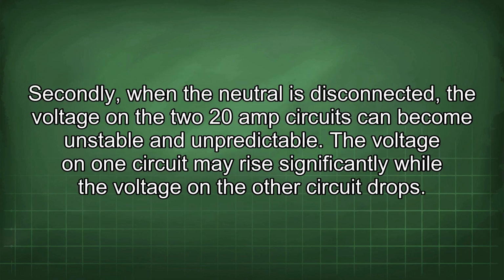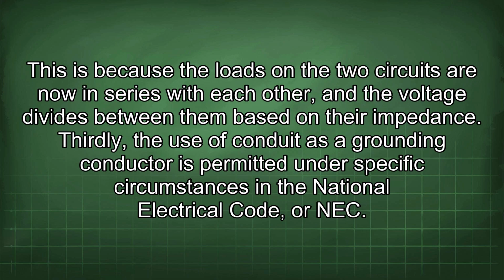Secondly, when the neutral is disconnected, the voltage on the two 20-amp circuits can become unstable and unpredictable. The voltage on one circuit may rise significantly while the voltage on the other circuit drops. This is because the loads on the two circuits are now in series with each other, and the voltage divides between them based on their impedance.